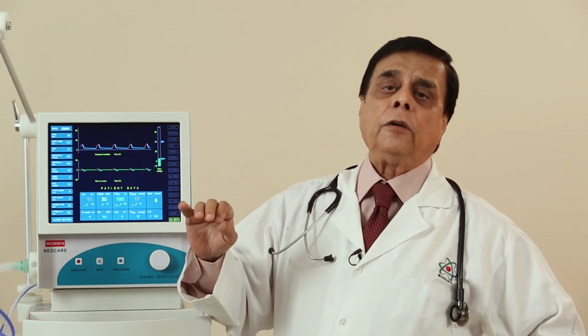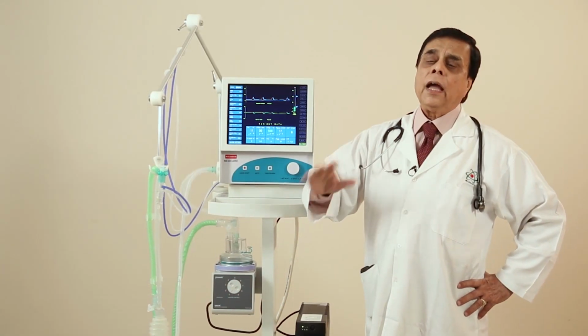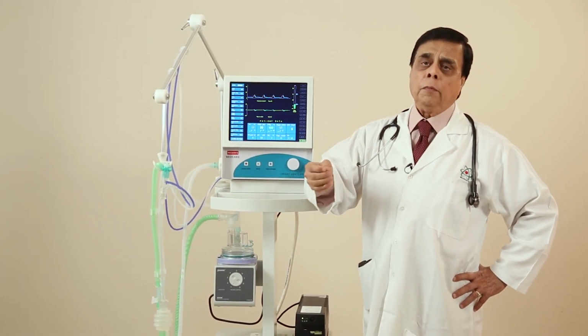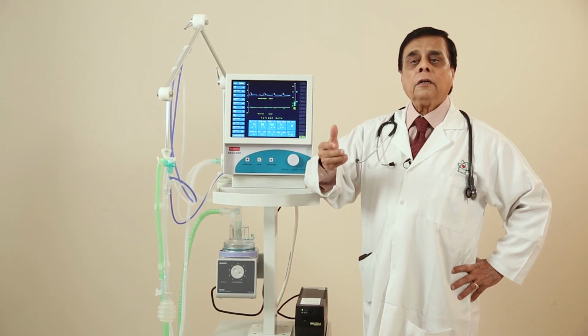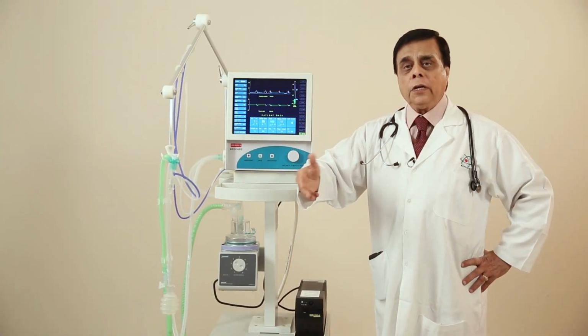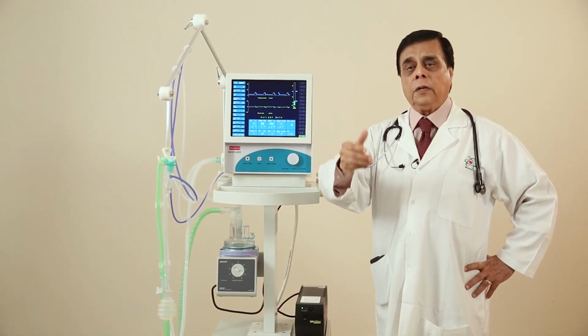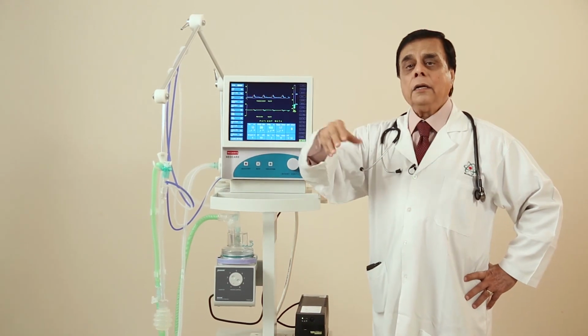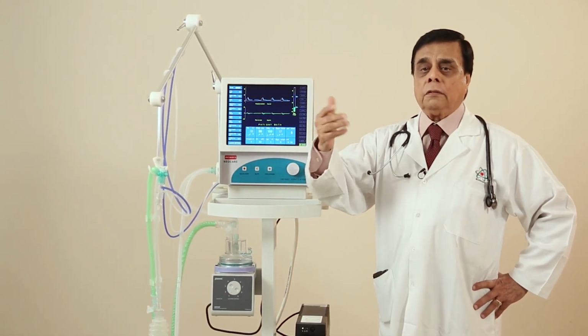But even then, if the patient needs a little bit more ventilation, we have incorporated a sensitive demand valve. And with that, with a small more demand of the child, the ventilation will be adequate. Now, we have made a pressure control preference. Why pressure control? Because we don't know their lung characteristics. That's why we can start with a low pressure control system and then step up slowly. And it stands to reason.